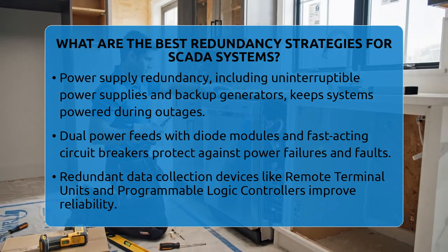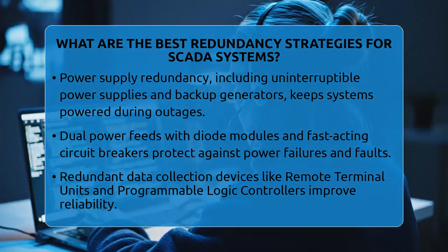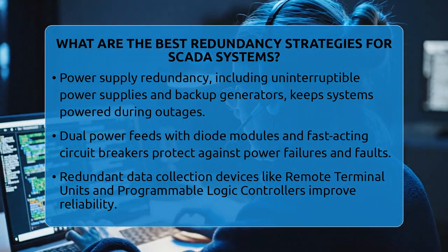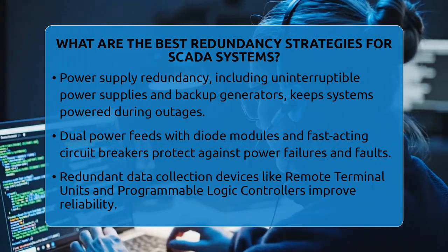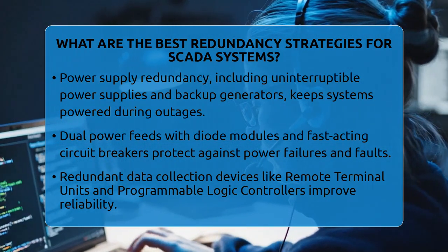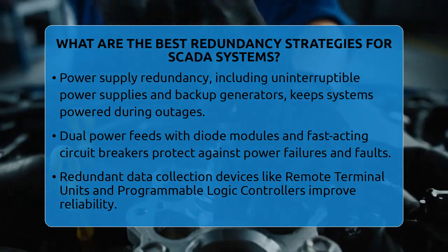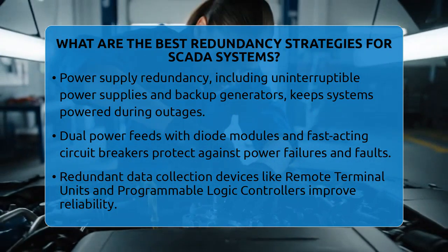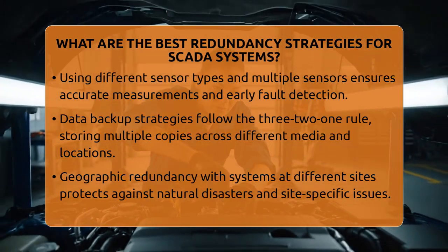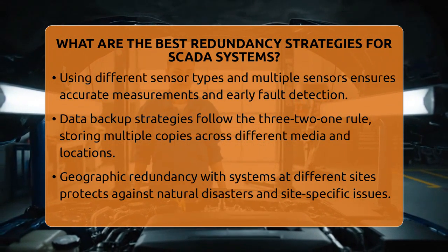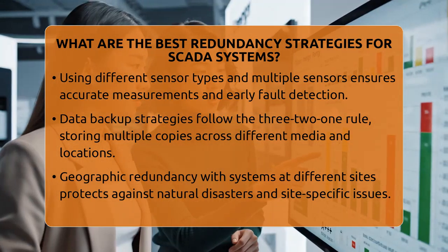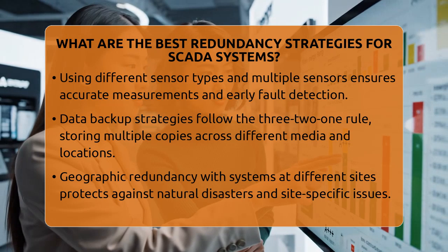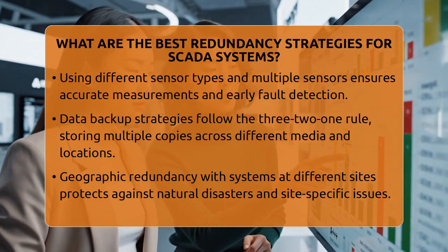Data collection devices like remote terminal units and programmable logic controllers should also have redundancy. Installing multiple sensors and controllers for critical measurements means if one fails, others can take over. Using different sensor types, such as ultrasonic or float switches, adds extra reliability and helps detect mismatches early.